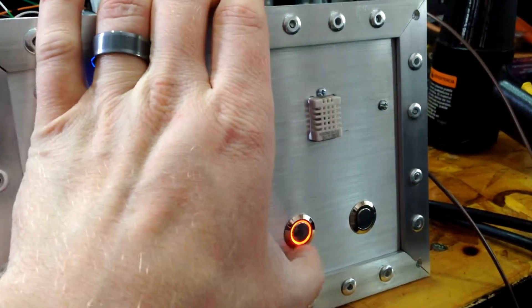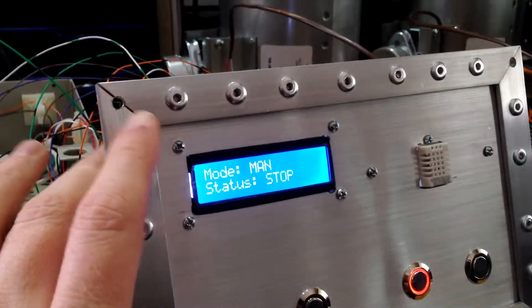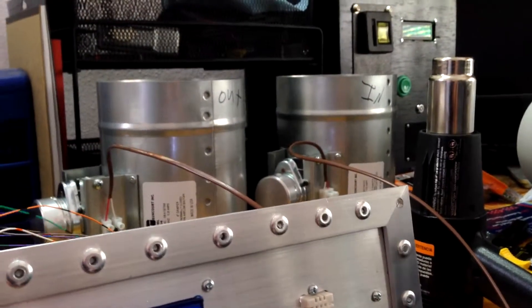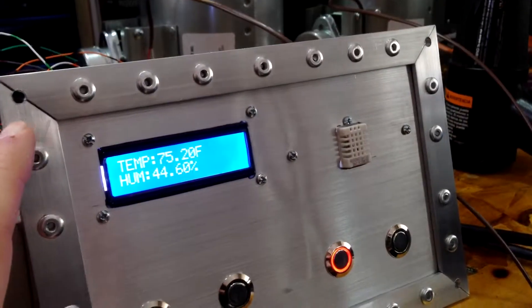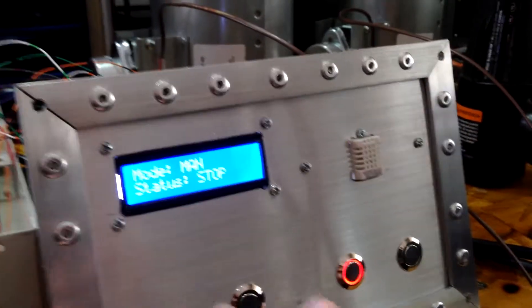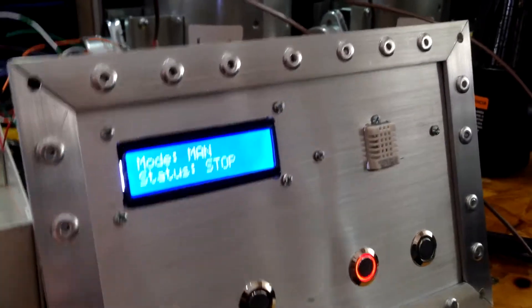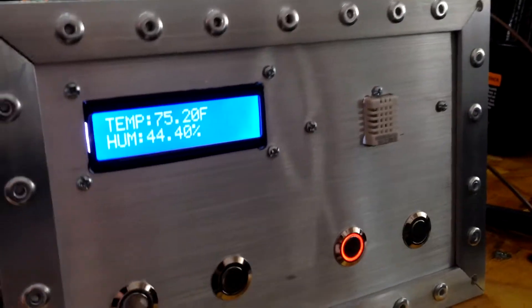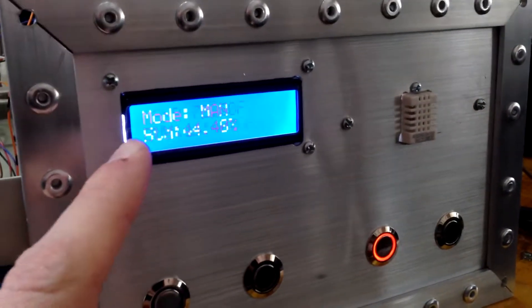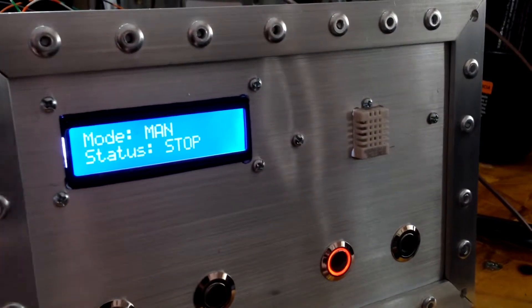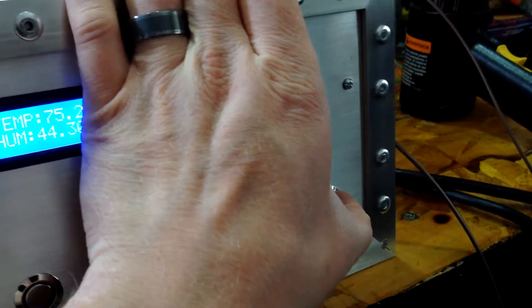Or if you do stop, then it'll just close everything. It'll depower the relays for the vents or the dampers. And it'll stop the fan. It'll depower the relay for that. And it'll put everything in the manual stop. And it won't do anything in this mode until you put it back into one of the other modes.